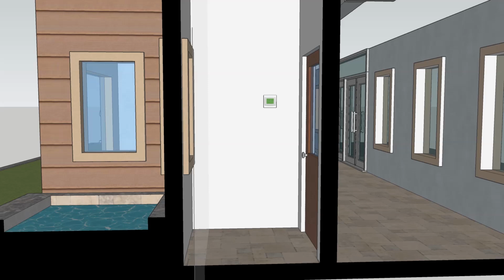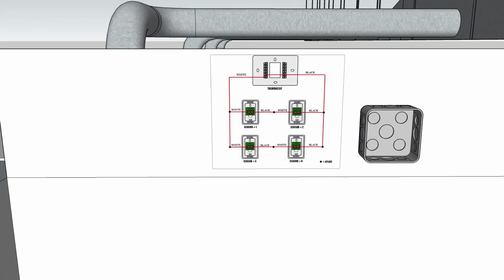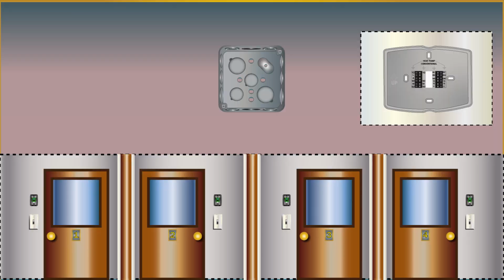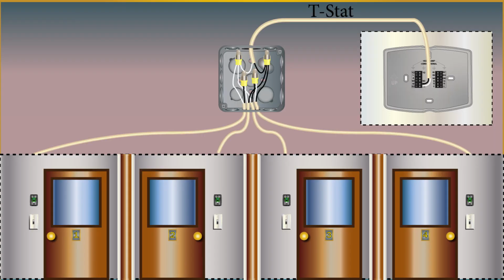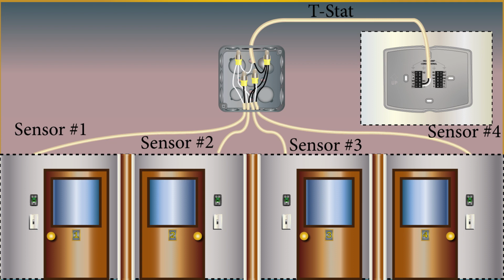Now above the location where the thermostat is to be mounted, either above ceiling tiles or in an attic of a home, that's where we'll mount the splice box. From there, run an 18-2 conductor down to the thermostat and label that wire T-stat. Then run another 18-2 wire to each temperature sensor location back to the splice box. Now label each wire sensor 1, sensor 2, sensor 3, and sensor 4. It doesn't matter which is which, just as long as each sensor has a unique label on each end.